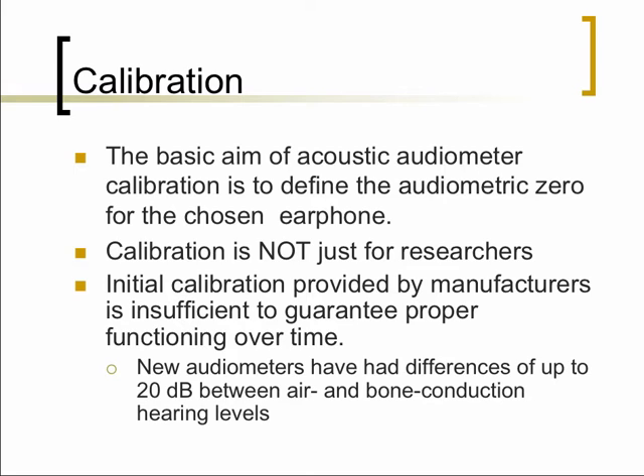So when one is calibrating, of course, the main aim is to define the audiometric zero for any given transducer. It could be earphones, it could be insert earphones, it could be a bone vibrator, it could be your speakers. And there is this wrong notion that calibration is just for researchers. No. Calibration is important for any clinician, including clinical audiologists. And the initial calibration provided by manufacturers is not sufficient for doing justice to your patient and for medical legal purposes.